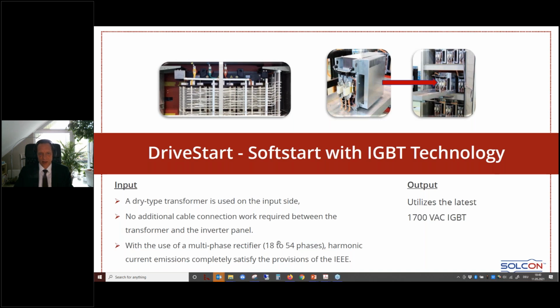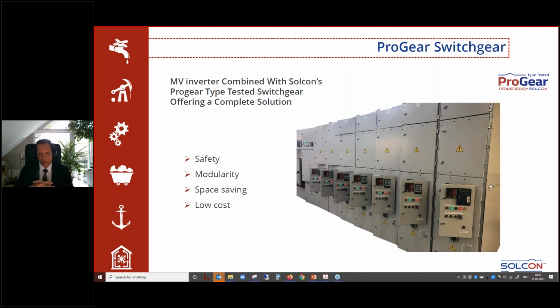And we can achieve from 18 pulse up to 54 pulses, very low harmonics, adhering to the IEEE 519 regulations, the newest edition. With the IGBT starter comes also a switchgear portion. I come to it in a moment. With our ProGear type medium voltage switchgear, we are delivering a complete solution, which is giving you safety, and it's modular. We can apply it to various configurations, either multi-start for many motors to be started with the same drive start, or a single motor solution, which is giving you a cost advantage.